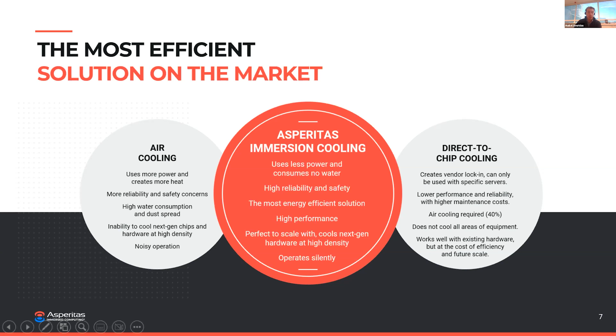So how does this work from our perspective? Again, single phase immersion cooling - there are different ways of circulation and methods within this space. It's not one solution fits all, but what we provide is natural convection based immersion cooling where there are no pumps involved. It's a very efficient way of cooling. There's basically no active component in there. So the hot components in the system are driving the flow within, and this is a self-managed system - more power means more flow, precisely from the places and locations in the server where flow is required.